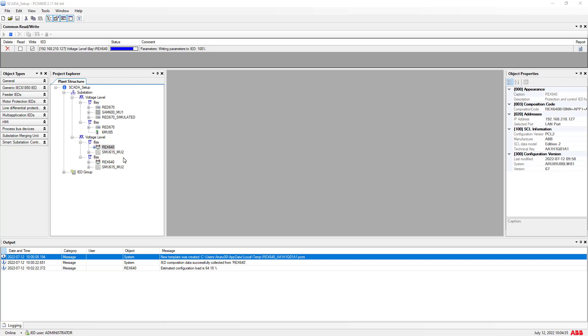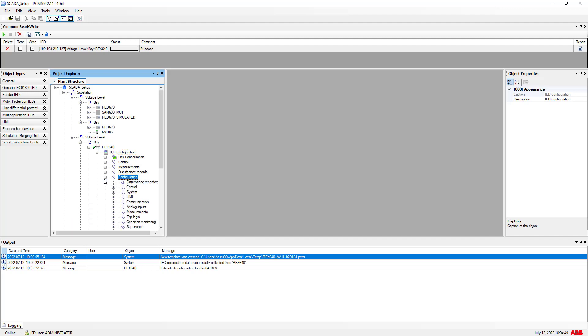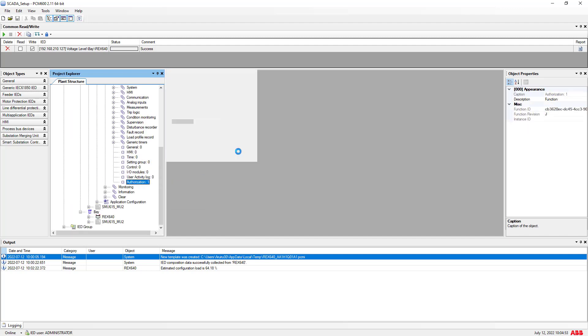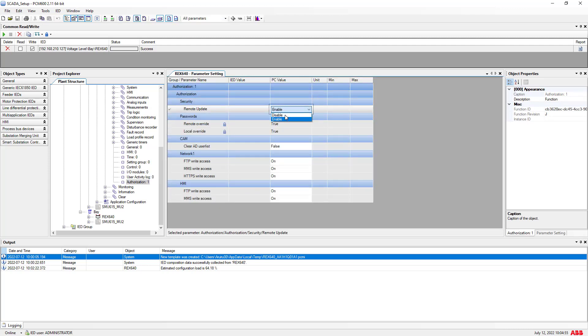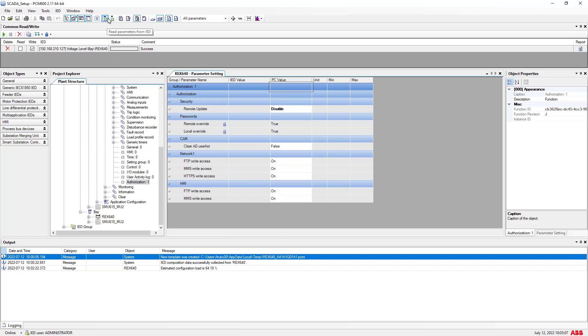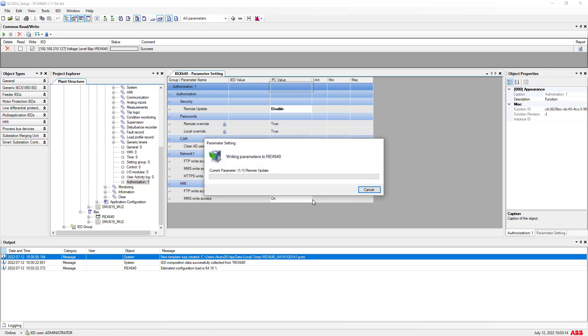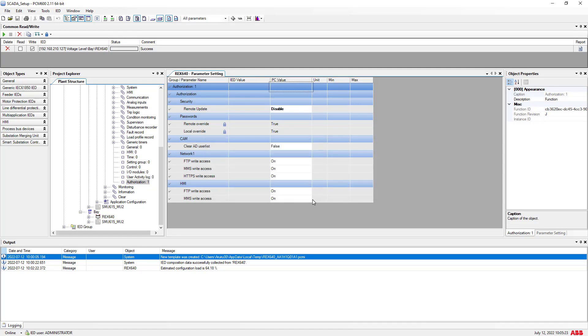After you update the firmware, it is also important to disable unused services. For example, the remote update that we enabled needs to be disabled later on in a real environment. Go back to the authorization setting and disable the remote update if you are not going to use it. You can also write the changed parameter or the whole function group values, and disable unused services and ports when using the IED in a real environment.